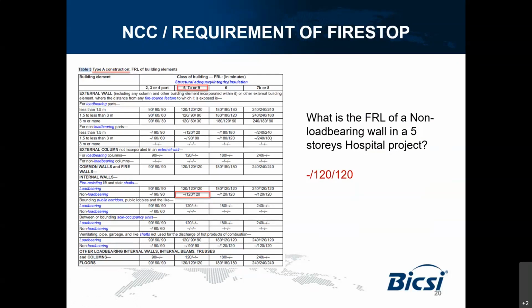It could happen that in a lot of projects, especially hospital or data center projects we always work on, they may use a high rated wall, but the actual building code rating is actually lower. I was involved in a data center project a few months ago. Initially the wall element they designed used a so-called 240 wall, but when we drilled down to that internal barrier, internal non-load bearing, do we need to give a 4-hour rated 240 penetration firestop solution? It may not need it.